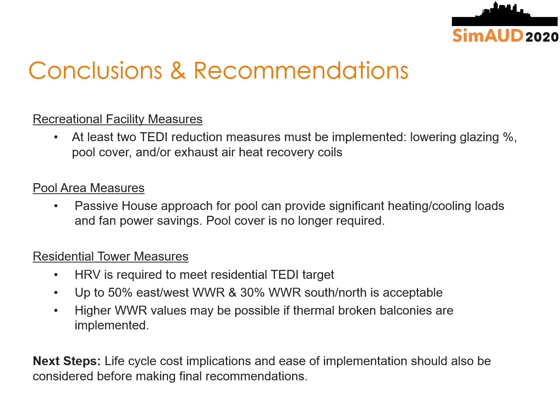Finally, for the residential tower, we looked at several options with a parametric design analysis, and we found that an HRV is required to meet the residential TEDI target, and that with the proposed envelope, 50% window to wall ratio on the east and west side is possible, and higher window to wall ratios may also be possible if thermally broken balconies are implemented.